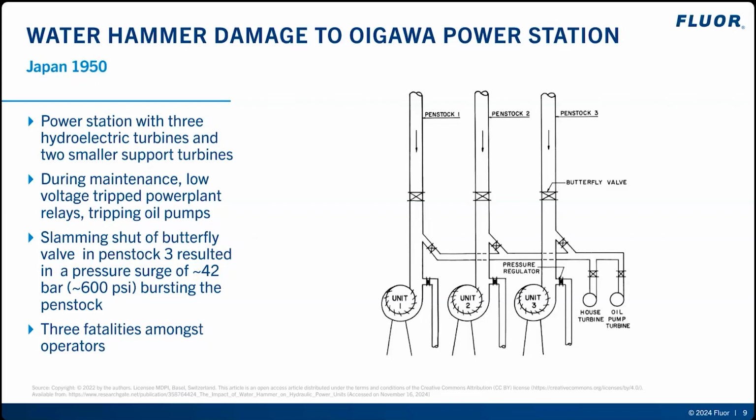Hydraulic surge was a known phenomenon even in the 1950s. And the butterfly valves installed in the penstocks were intentionally designed to have a closing time of no less than 28 seconds to prevent hydraulic surges. Unfortunately, as its oil cylinder was empty, it instead closed nearly instantaneously.